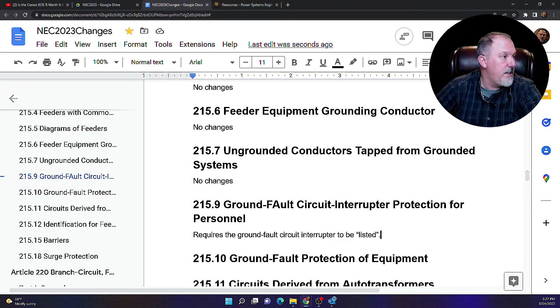And that didn't change. 215.10. 215.10 moved the 600 volts maximum to 1000 volt maximum in accordance with other areas of the NEC that made this same move in voltage level. In addition, the informational note was also modified for clarity, no intended change in the informational note other than meeting the requirements of the style manual. Okay, that's all we did in 215.10. Piece of cake.